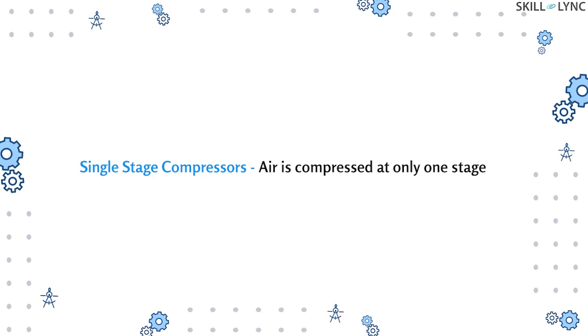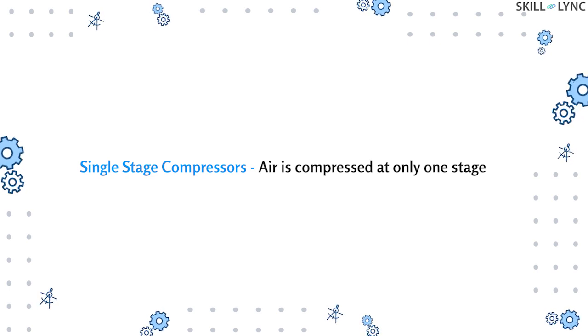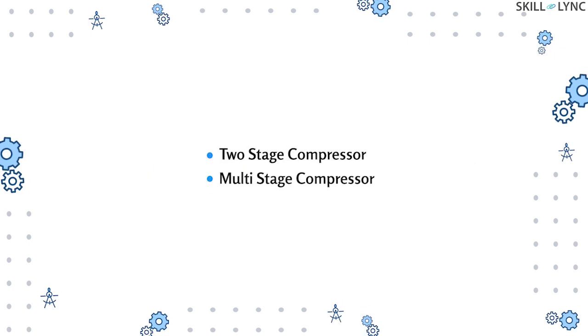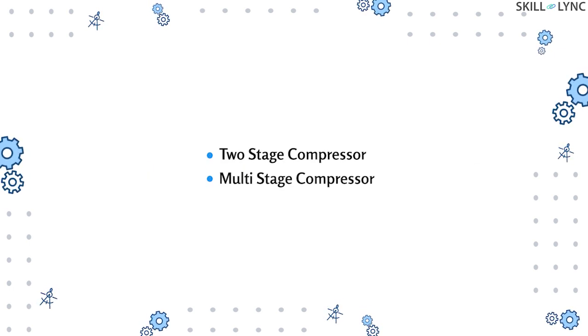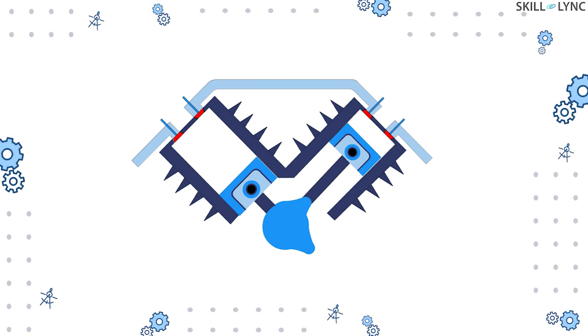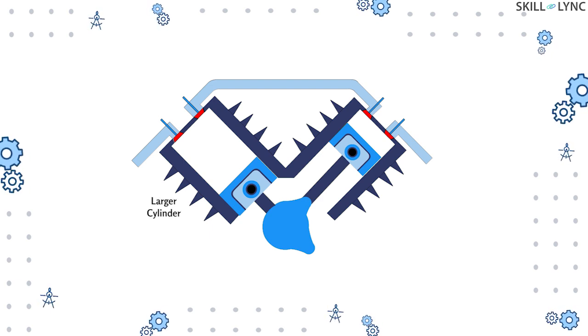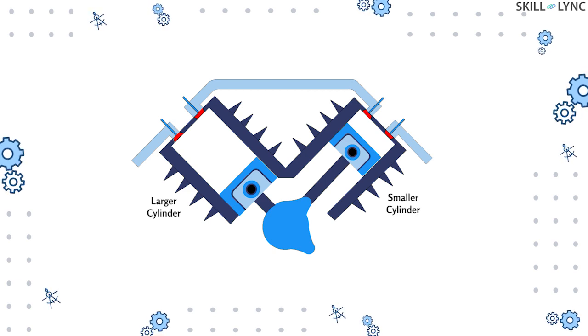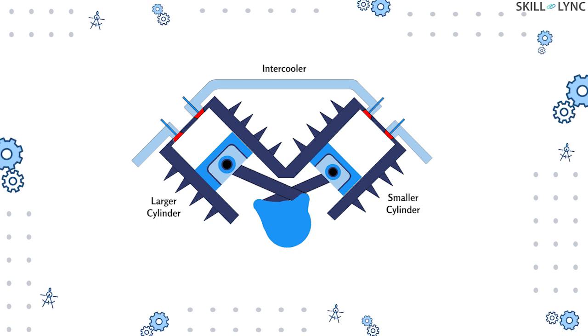So far we've discussed single and double acting compressors where the air is compressed only once — these are single stage compressors. For obtaining compressed air of high pressure, two stage and multi-stage air compressors are used. A two stage compressor uses two cylinders of different sizes, both provided with individual suction and delivery valves. The delivery valve of the larger cylinder is connected to the suction valve of the smaller cylinder via an intercooler.